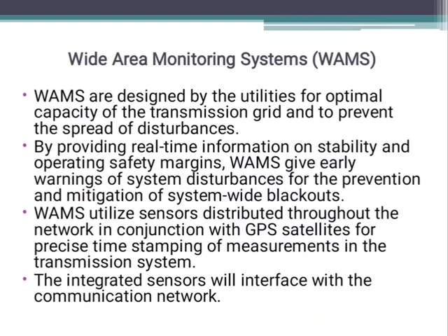Now let us discuss one of the most important devices in the transmission system, that is the PMU. The long form of PMU is the phasor measurement unit. It is also called a synchrophasor. This device will take a snapshot of the power system. Let me brief once again. Whatever the bus voltage is, the phasor of that bus voltage and the branch current, the phasor of the branch current, some additional information like the location and other network parameters, all are monitored by the PMU. Along with the bus voltage and bus current, it will take the phase angle also. That's why it is phasor measurement. Along with the magnitude, it will take the phase angle also.